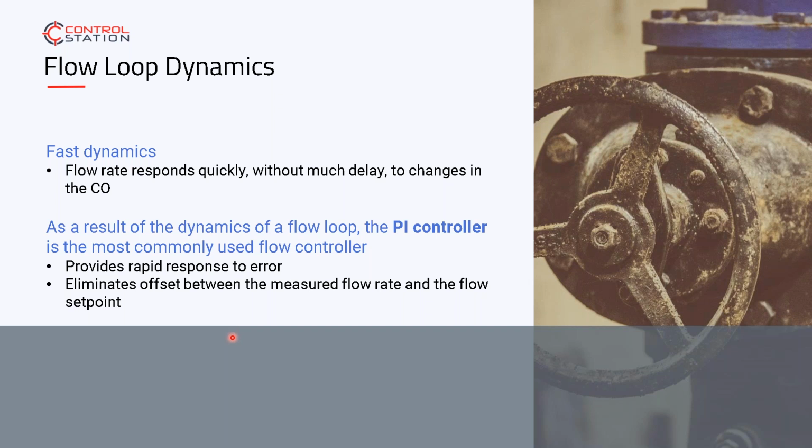It's something that you see regularly: the flow loop reacted in, the time constant was 3 seconds. So that's how I worked to control in that speed. But the downstream system was a 3-minute system, so there's no way it can deal with those changes. Just because you can doesn't mean you should, is what I would say to it. Think about where that flow loop is in your process.